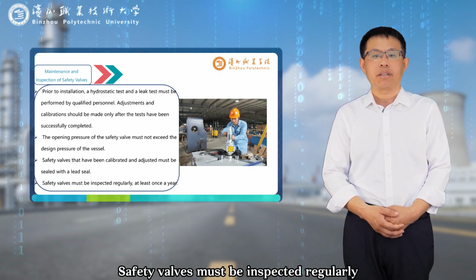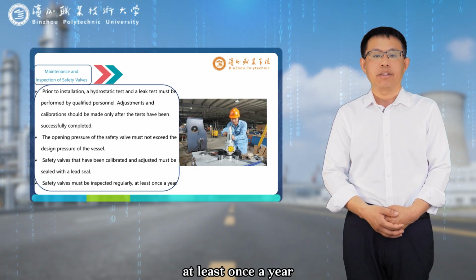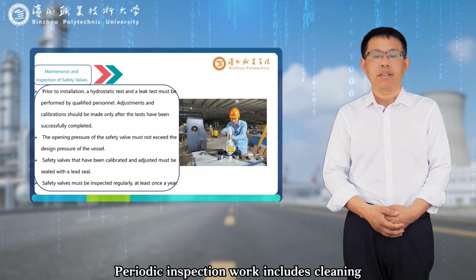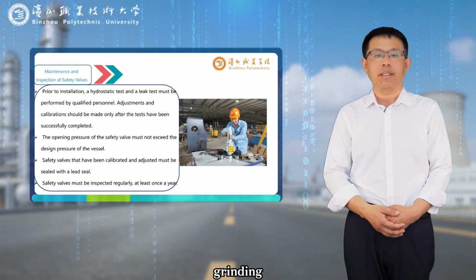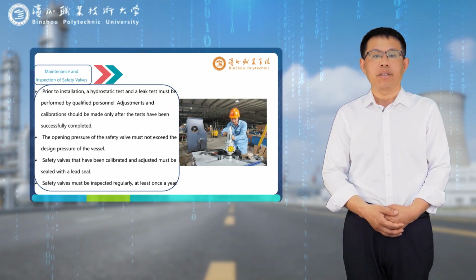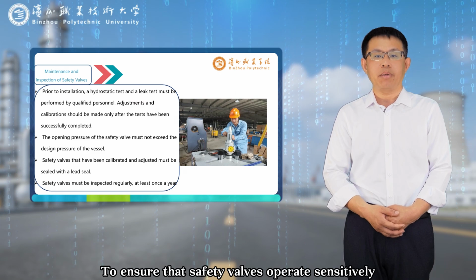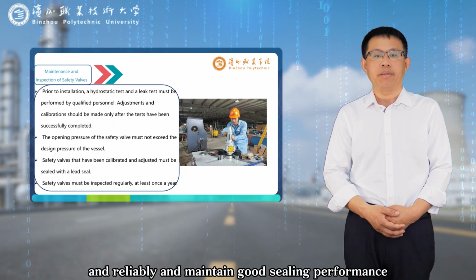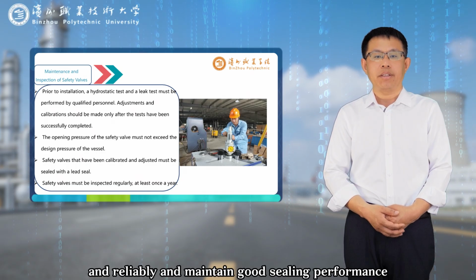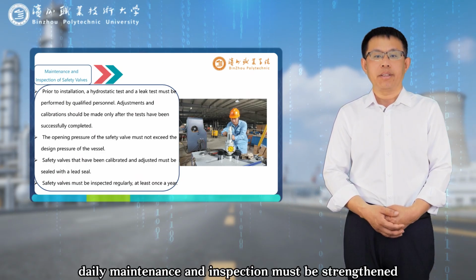Safety valves must be inspected regularly, at least once a year. Periodic inspection work includes cleaning, grinding, testing, and calibration.